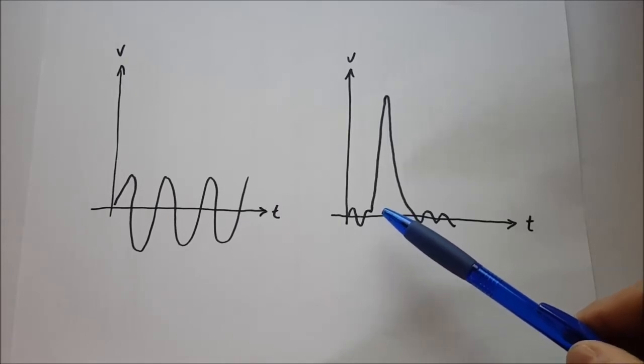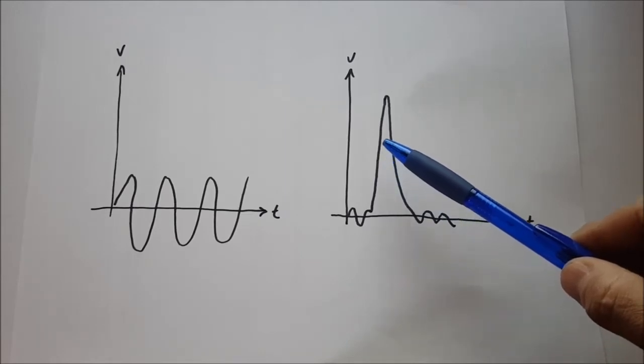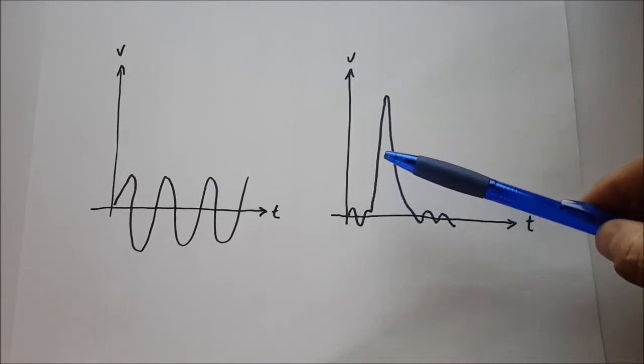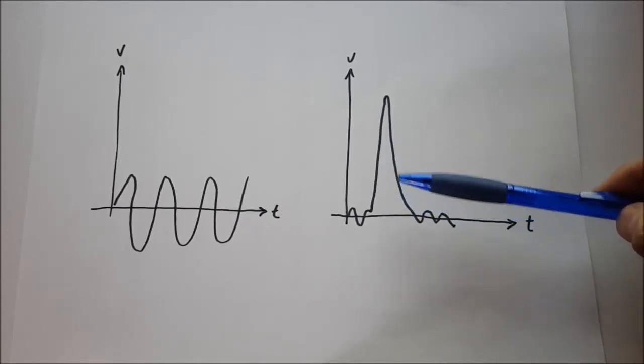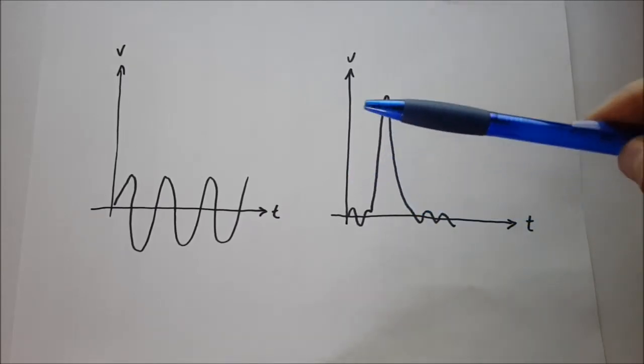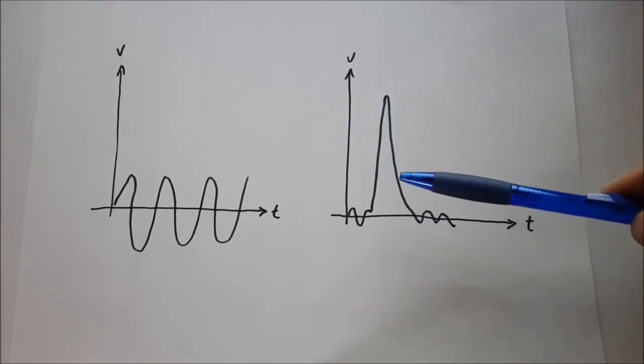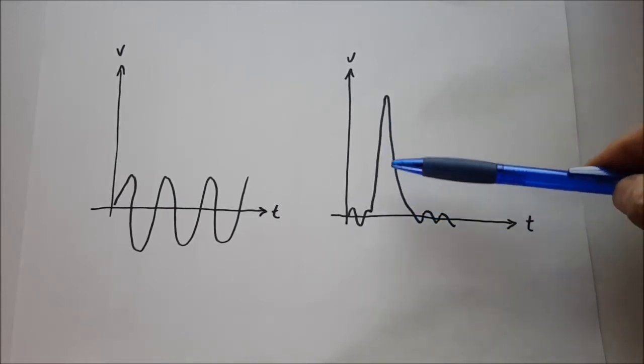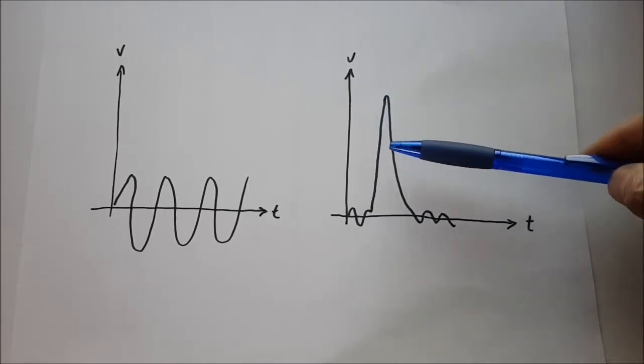The magnetic field starts to induce very rapidly a voltage surge on our electrical system. So the voltage is rising, rising, rising. Where does the energy come from? Well, not from our system internally. It comes from outside, it comes from the lightning via the magnetic field.